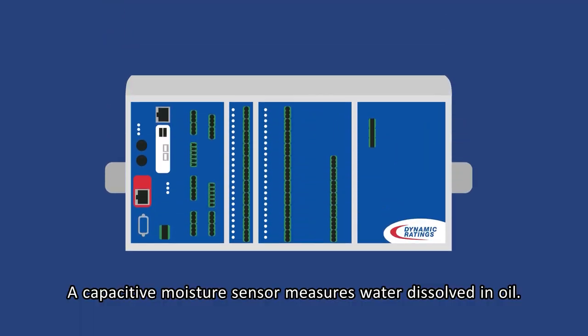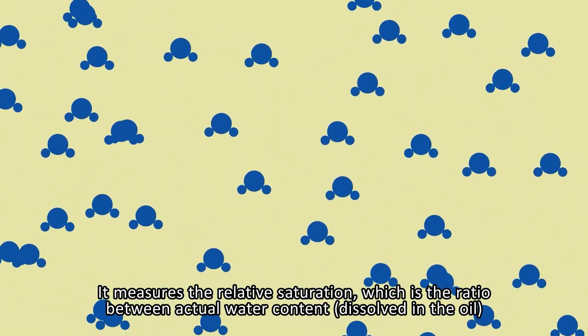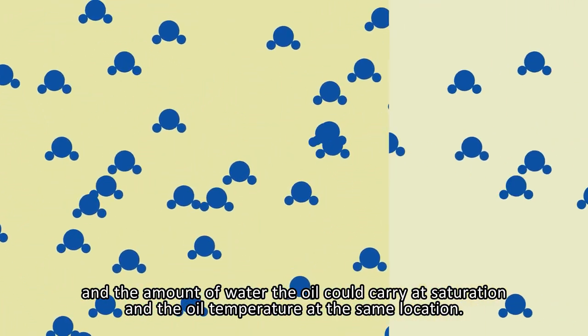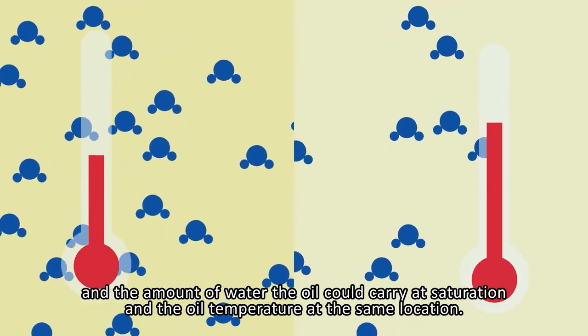A capacitive moisture sensor measures water dissolved in oil. It measures the relative saturation, which is the ratio between actual water content dissolved in the oil and the amount of water the oil could carry at saturation and the oil temperature at the same location.